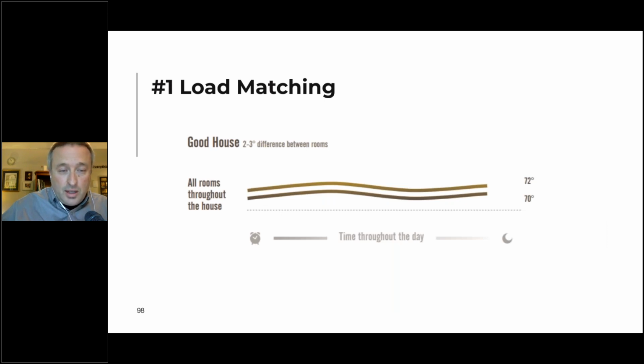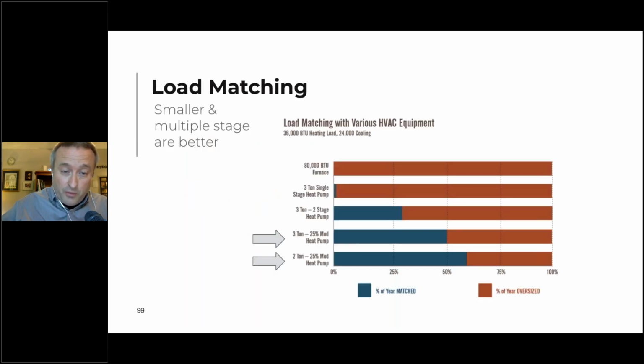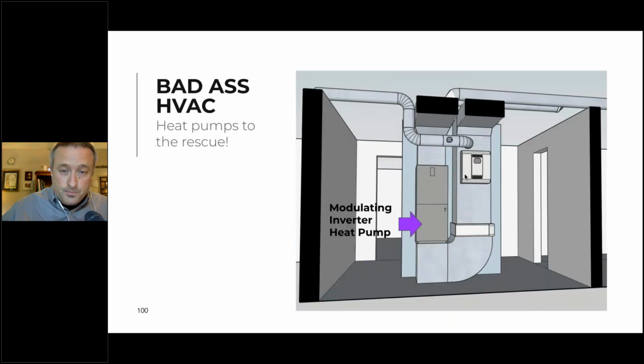If you want that load matching we were talking about, where all the rooms are within a couple degrees of each other, you need right-size, multi-speed equipment, preferably very aggressively sized, like that 2-ton - the more aggressive you can get, the better. That's best done with a modulating inverter heat pump, and every manufacturer makes a number of these.